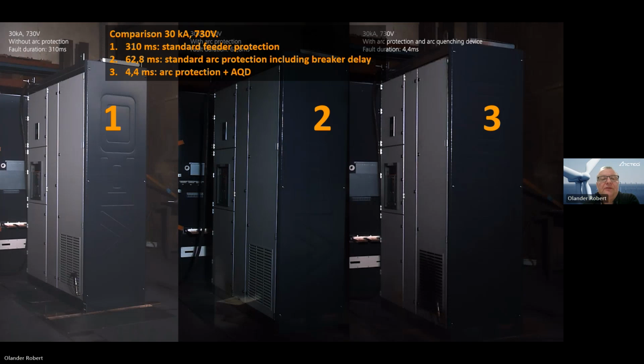And so here we have three different versions, same switchgear and same current and everything. In the first one, we have only overcurrent protection relay, 310 milliseconds. In the second one, we have an arc protection system. So then, including breaker delay, we will have 62.8 milliseconds time for the arc. And then in the third one, we have a quenching device, an AQD, and there we will have 4.4 milliseconds protection time.